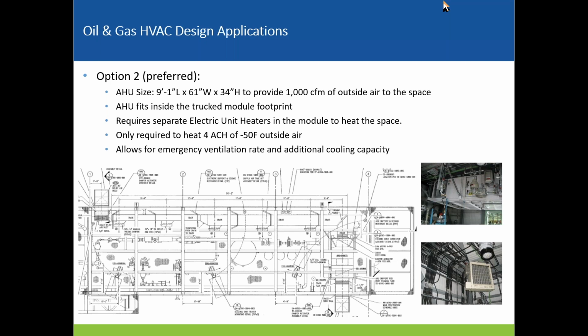You do require separate electric unit heaters, so you do have space considerations for these and your NEC working clearances to the connections. But you're only required to heat 4 air changes per hour, minus 50 degree outside air. And it adds some benefit because, let's say, with a 40 degree discharge air temperature at minus 50, you're going to get roughly 12 air changes per hour. The unit's going to be roughly the size for 12 air changes per hour. And 8 recirculating and 4 coming in.